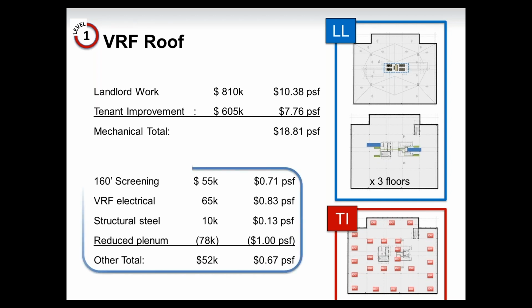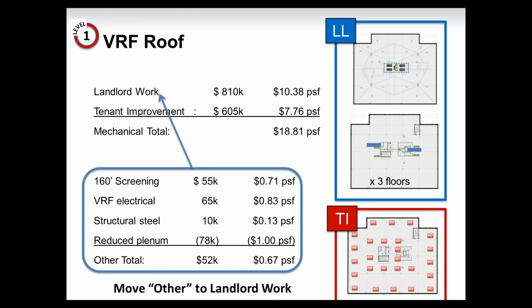We again take these other costs, which is a reduced amount for screening. Electrical is actually slightly higher. It takes a little more to run the power wiring to 24 VRF units than it does to 2 rooftop units. Structural steel is a little bit less. The VRF equipment weighs less than the rooftop units, so we save some money there. And then we've got the reduced plenum savings of $1 a square foot.